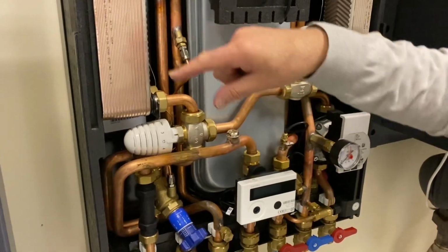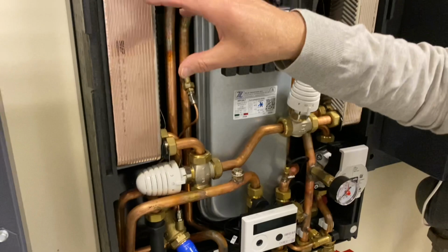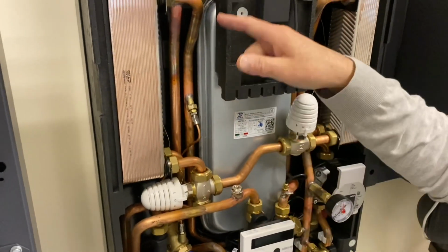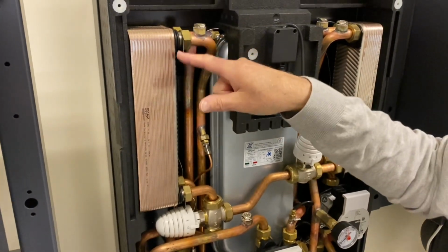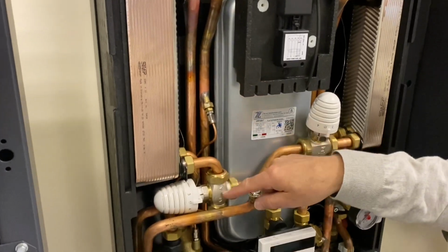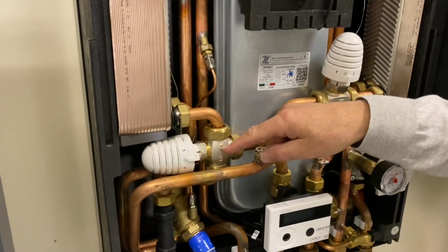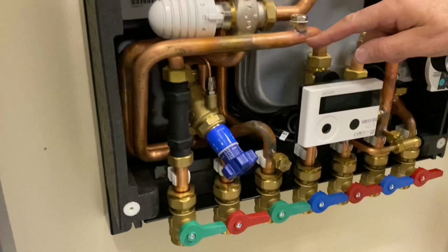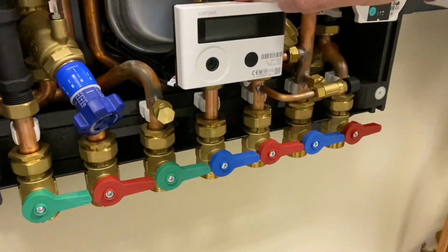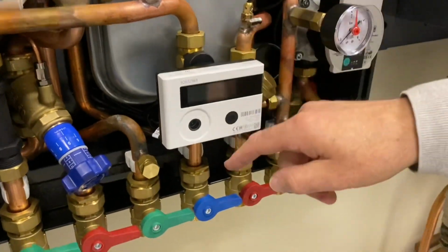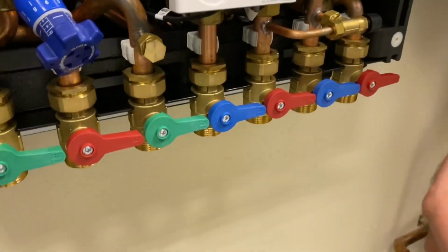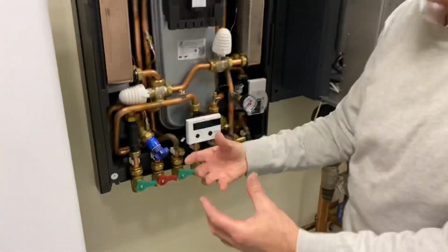So, cold water in, heated up by the primary water in the plate, hot water out, primary water in, primary return out to this proportional valve, and then back down to the return through the heat meter here, back down to join into the primary flow returns around the building.